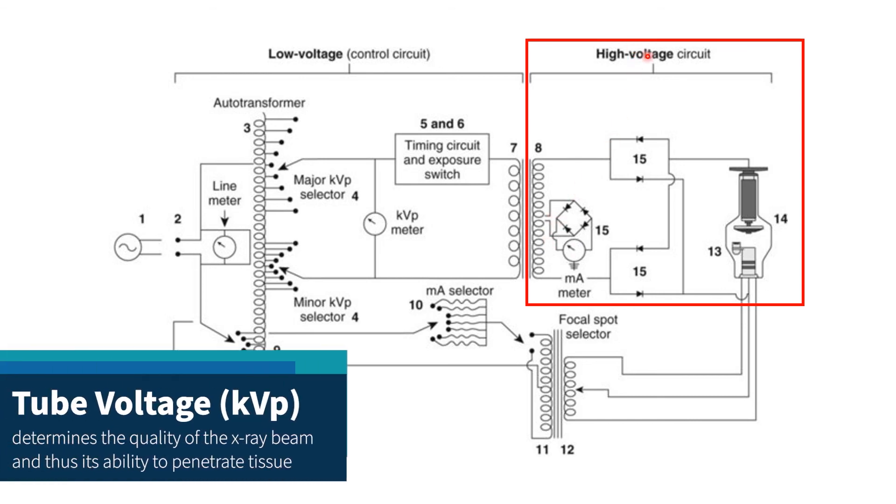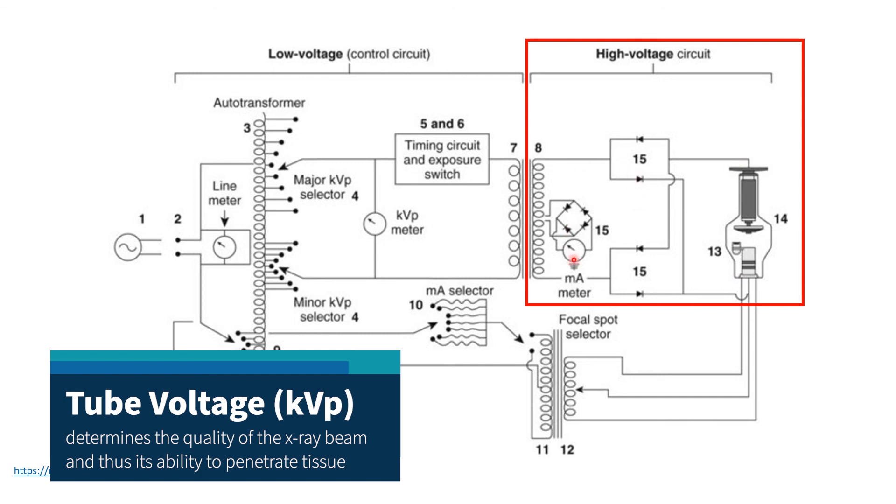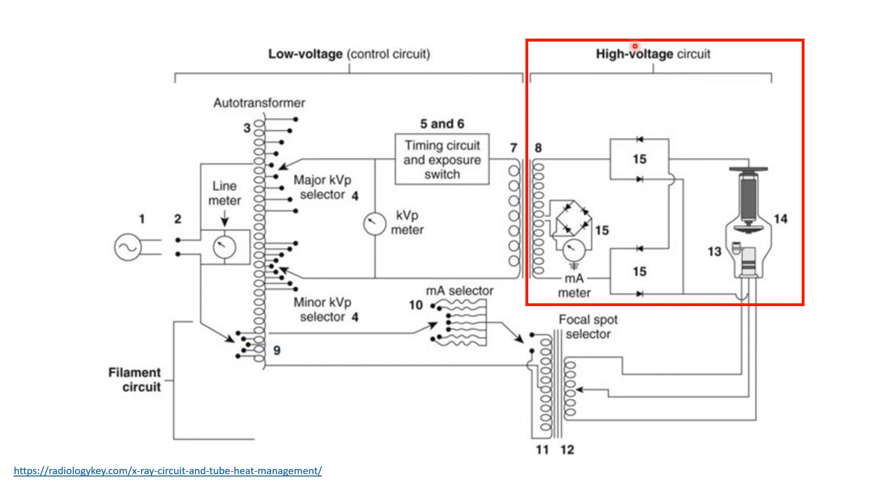We have the X-ray tube here and the rectifier unit. The current flows in the circuit only during an exposure. This is a dangerous circuit because of the very high voltage KV. Thus, high insulation for the cables is needed.